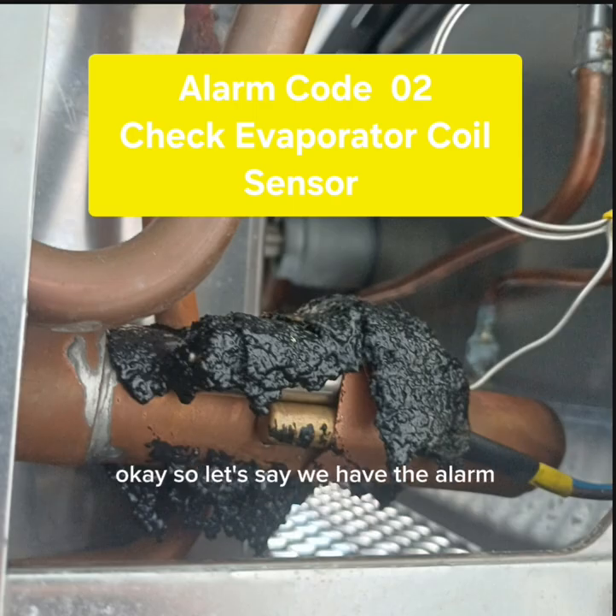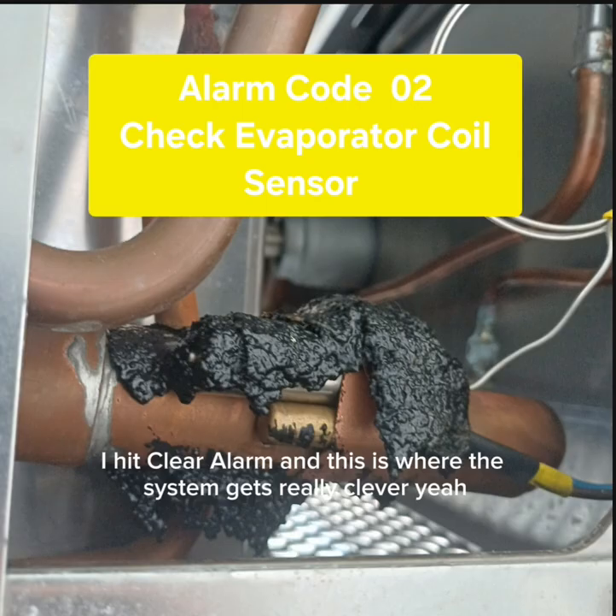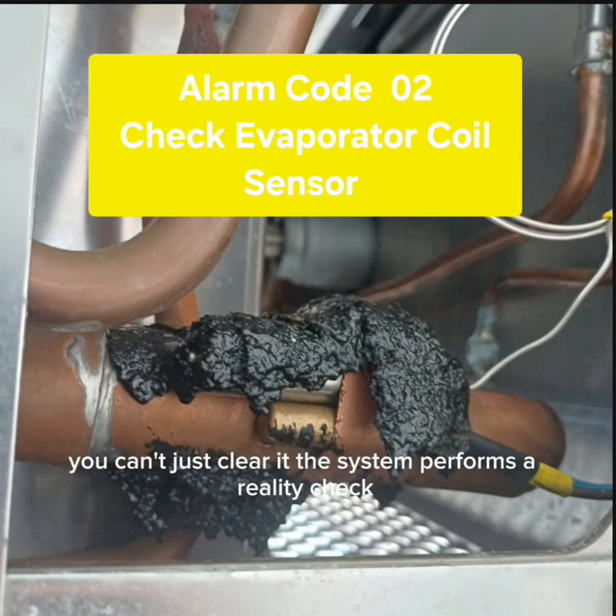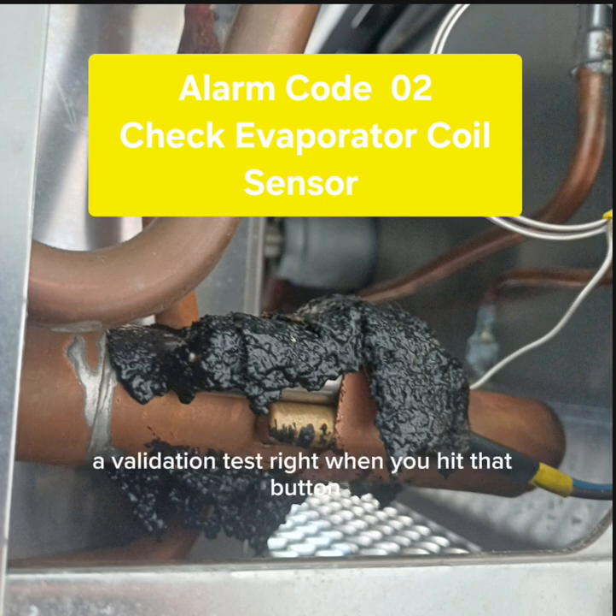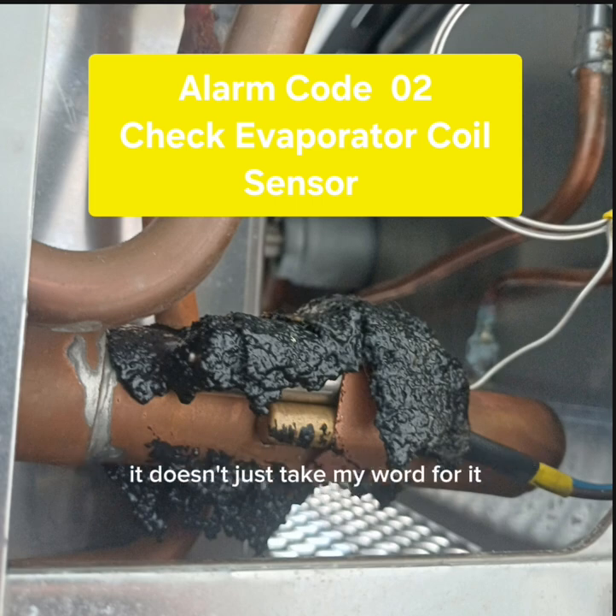Okay, so let's say we have the alarm. I think I fixed it. I go to the keypad, I hit clear alarm. And this is where the system gets really clever. Yeah. You can't just clear it. The system performs a reality check, a validation test, right when you hit that button. It doesn't just take my word for it. No, it trusts, but it verifies.